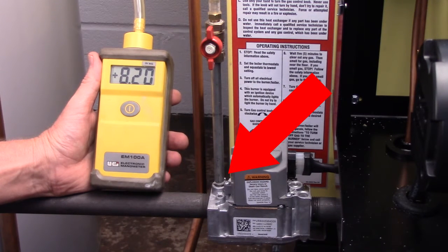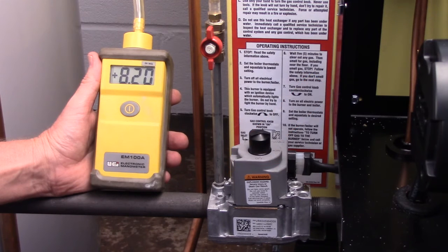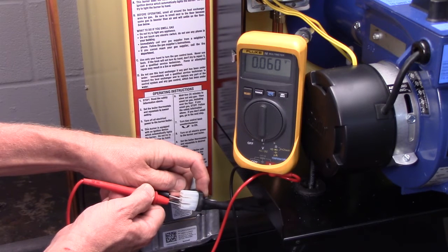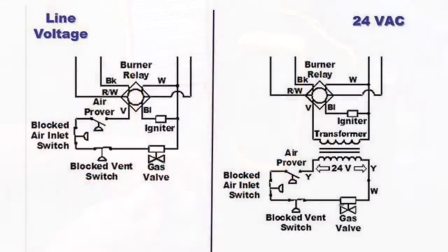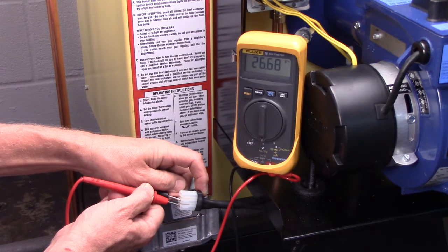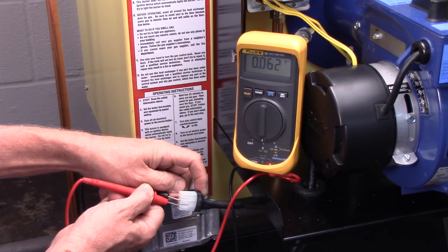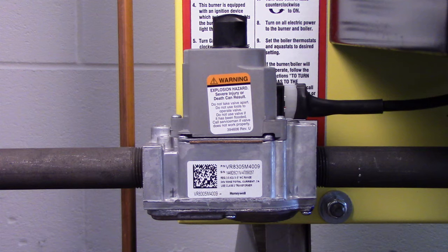If the pressure is in excess of 14 inches water column, it will cause the valve to lock up. Also, check that the gas valve is receiving the correct voltage during the trial for ignition period. Remember, in 2014, a 24 volts AC gas valve replaced the previously used 120 volts AC valve. If the correct voltage is present, with the inlet pressure below 14 inches water column and the valve still won't open, replace the gas valve.